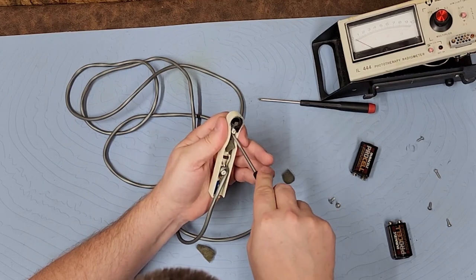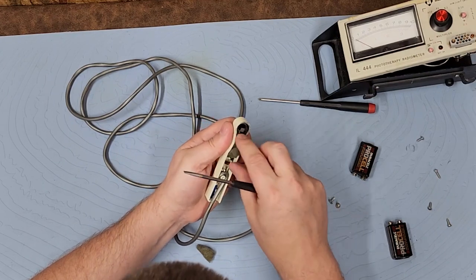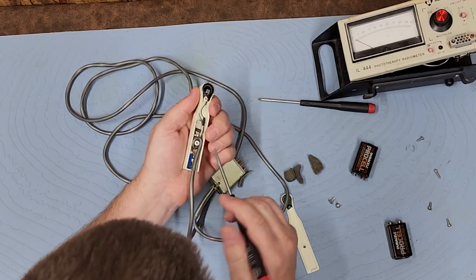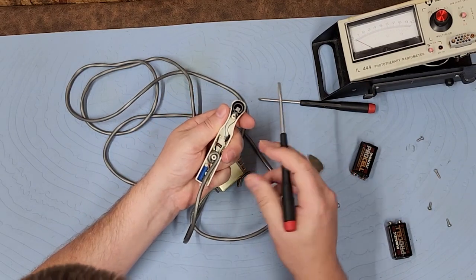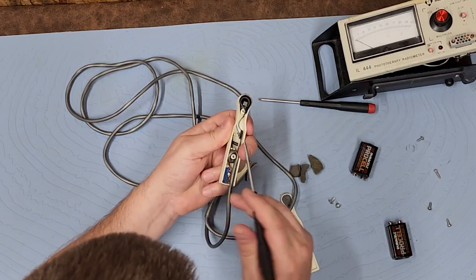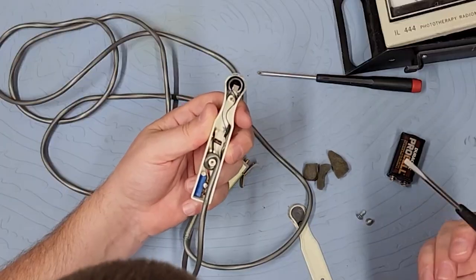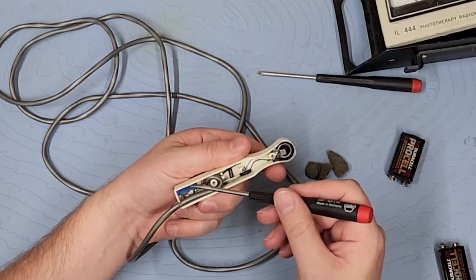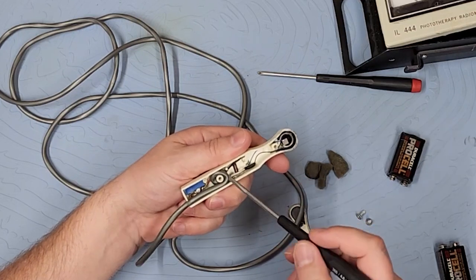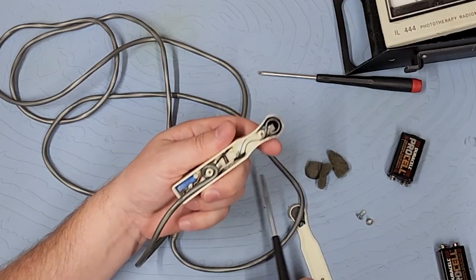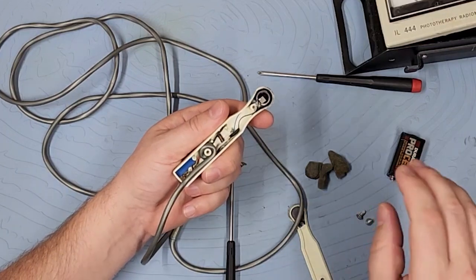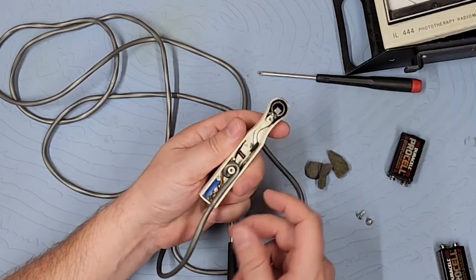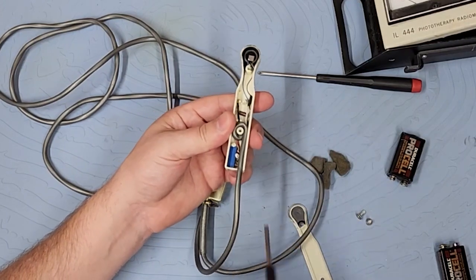I'm trying to be kind of delicate and drag this stuff out. I have the strain relief wrapped around one of the case standoffs. Down at the bottom I have a gain adjustment right here. So I'm curious - you calibrate this guy, yes, but I wonder if a lot of the calibration is done right here on your probe itself instead of over there at the base unit.